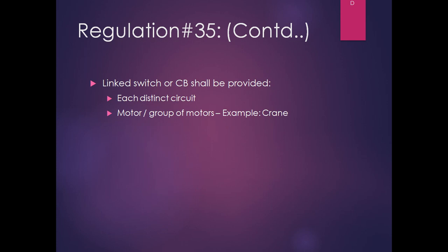Linked switch or circuit breaker shall be provided for each distinct circuit and motors or group of motors. The example for group of motors can be crane. In crane there is one forward direction motor, one backward direction motor, or maybe there may be one motor which can serve for forward and backward direction, one motor for left and right direction, and one motor for up and down direction. Then these three motors become a group of motors. For group of motors, at least there should be one circuit breaker.